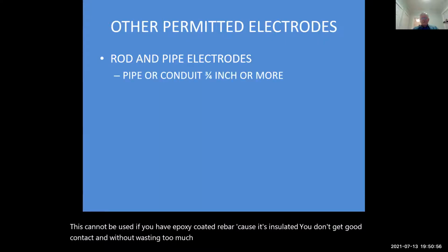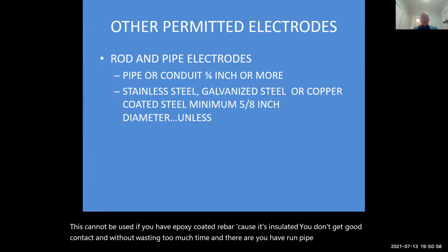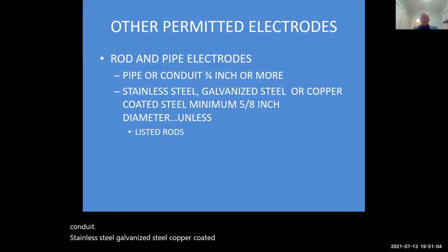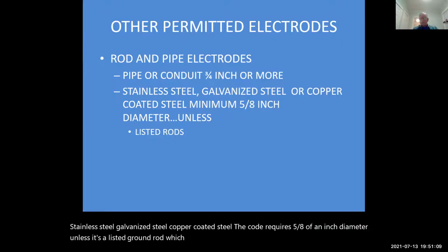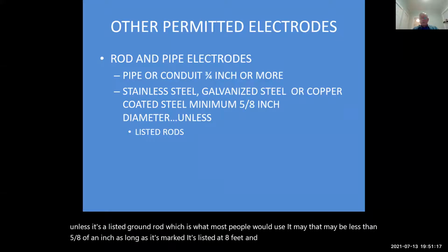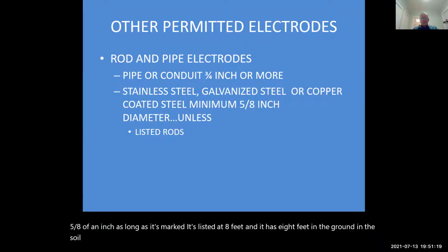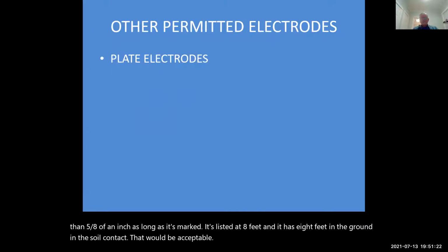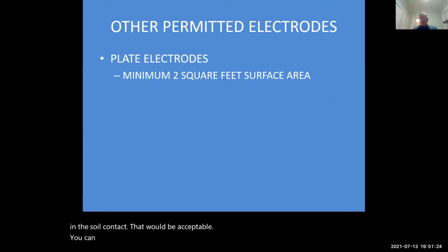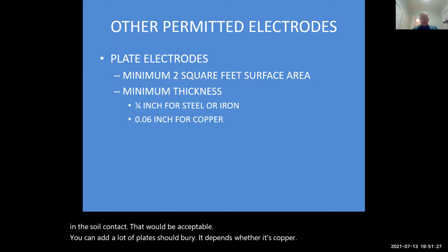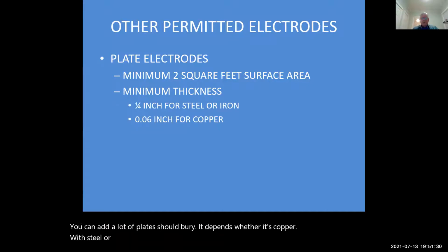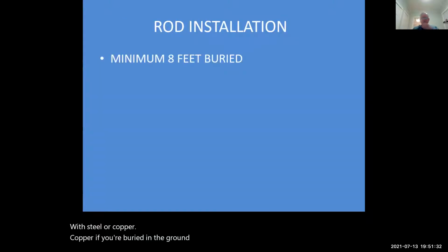And you have rod and pipe electrodes, pipe or conduit, stainless steel, galvanized steel, copper coated steel. The code requires 5/8 of an inch diameter, unless it's a listed ground rod, which is what most people would use. That may be less than 5/8 of an inch, as long as it's marked, it's listed 8 feet, and it has 8 feet in the ground in the soil contact. That would be acceptable. If you had a lot of plates, you could bury it. Depends whether it's copper or steel. Copper, if you bury it in the ground, someone will probably dig it up and take it.